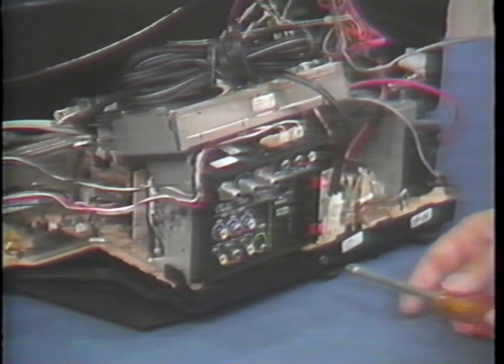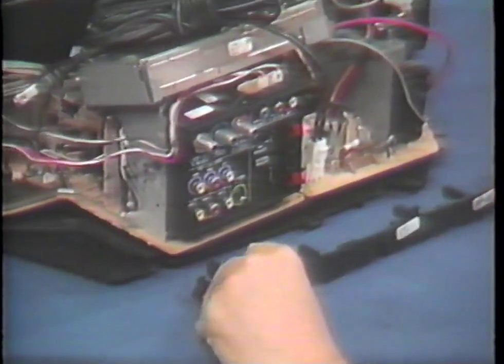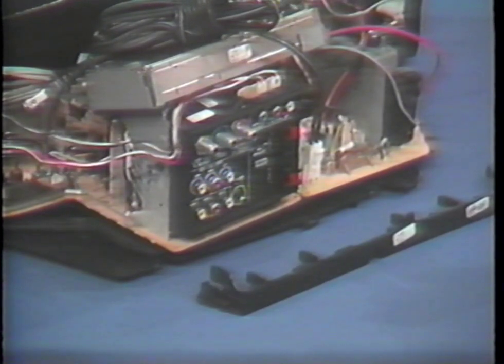In order to gain access to the modules for replacement, this guide rail here at the back must be removed. It's held in position with one 1/4 inch hex screw. Start out by removing that screw. Once that screw is removed, this guide rail can be removed by putting pressure down here on the left-hand side on the main chassis frame while lifting up on this guide rail. Then it will unsnap and remove from the main frame.